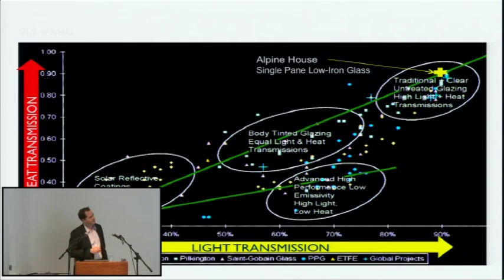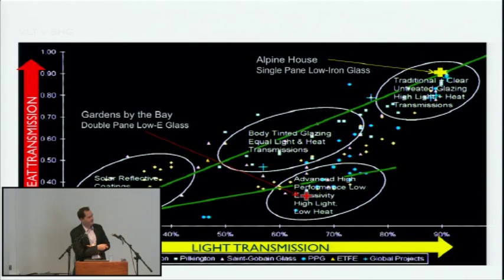And we'd just completed with Wilkinson Eyre a few months before the Alpine House at Kew Gardens, which used an incredibly transparent glass, which again is a cooled glass house. But we used very transparent glass there, while for Singapore, we were using a very spectrally selective glass. So a glass that lets in about 65% of the daylight, but only about 30% of the heat contained within solar radiation into the building, which was a good way of reducing heat load. But again, we had to make sure we were maximizing that 45,000 lux criteria.